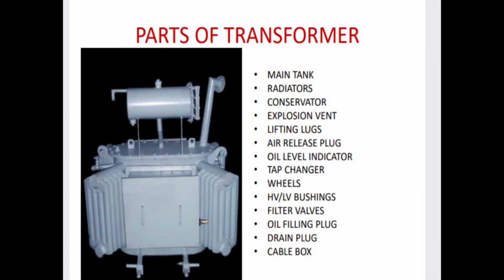So the parts of transformer. First is main tank, second is radiator, third is conservator, fourth is explosion vent, fifth is lifting lugs, sixth is air release plug, seventh is oil level indicator, eighth is tap changer, ninth is wheels, 10th is HV LV bushing, 11th is filter valve, 12th is oil filling plug, then drain plug and cable box.